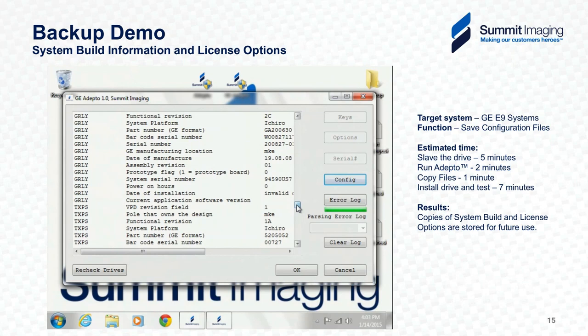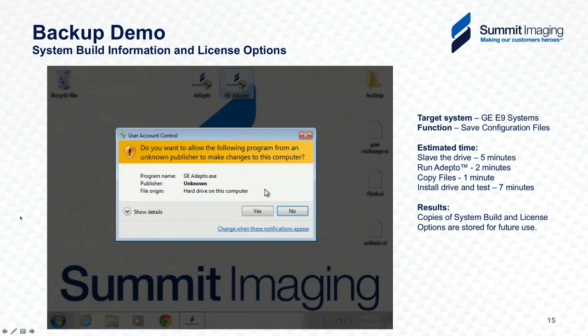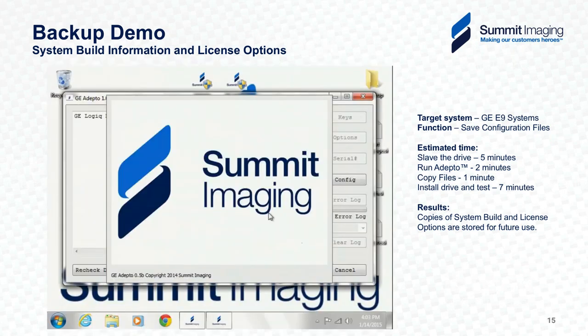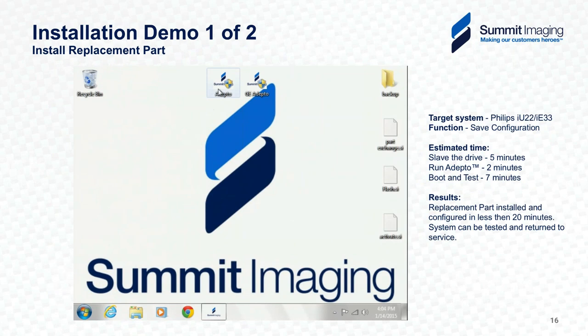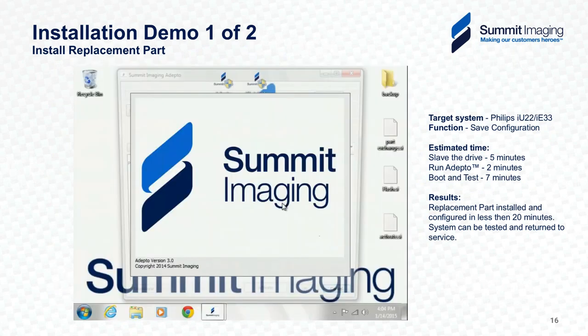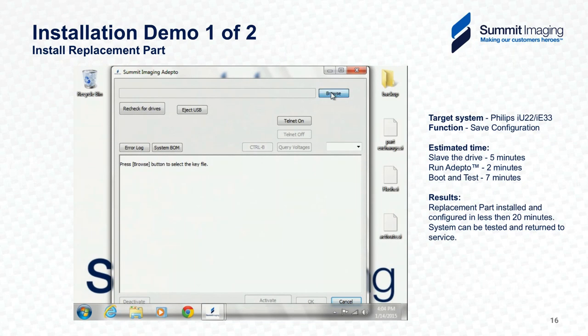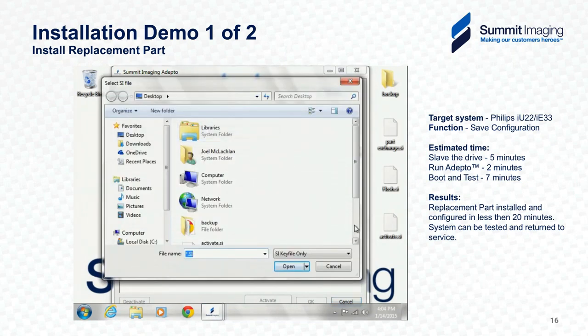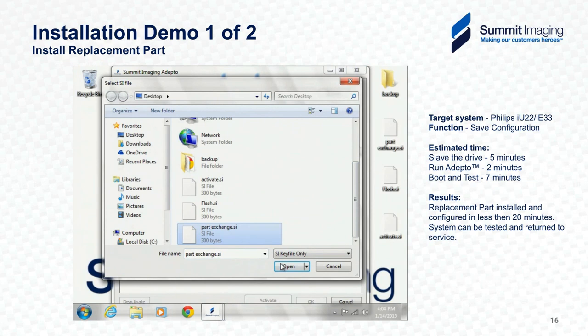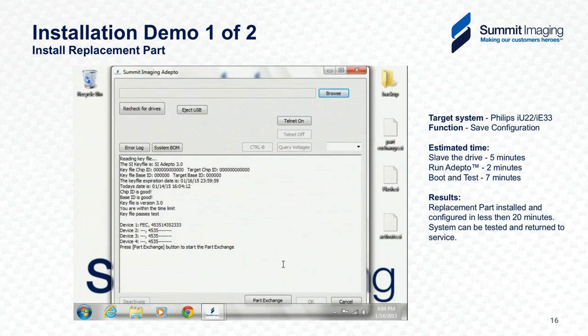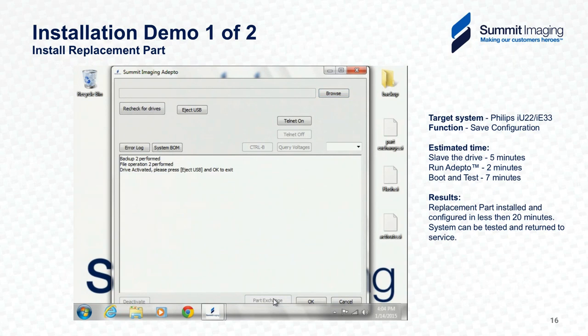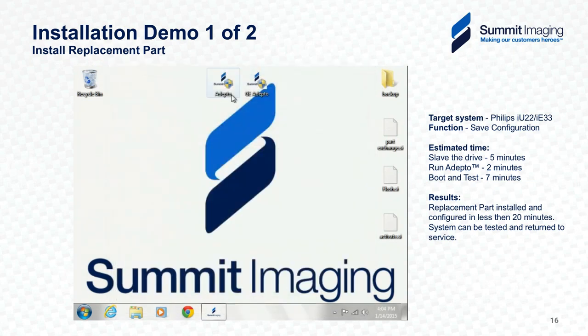Moving on to the next step. After you troubleshoot and save configuration, you're going to have to install that new component. So in this example, we're doing a save configuration on an iU22 and iE33. This is when you've actually installed a new board, say an A board. What we're going to have to do is pull the hard drive, run Adepto. It'll install the new part, which in the past could have been a quite timely process, even using the OEM service software.